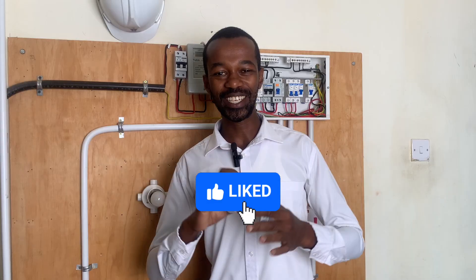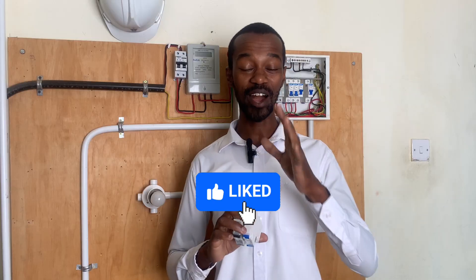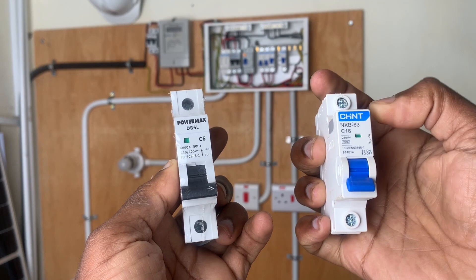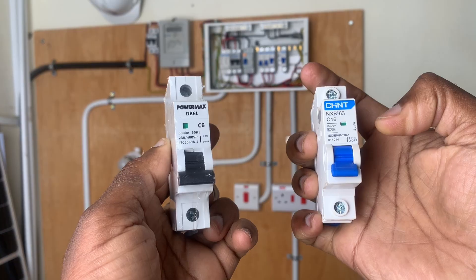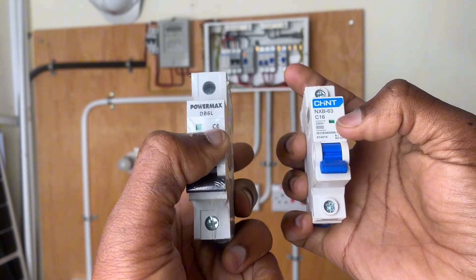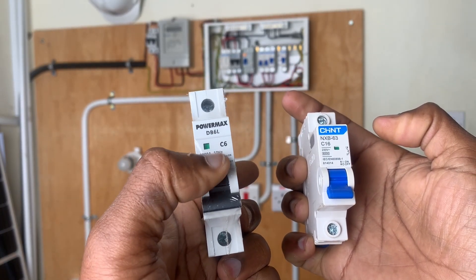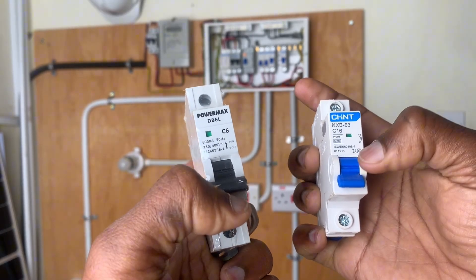An MCB is very important, and the size of that MCB matters. I have two MCBs here — a 6 ampere and a 16 ampere. They are from different brands: Powermax and Chint. But that doesn't matter as much as the numbers. The 6 ampere means it can only allow less than 6 amperes; anything above this will definitely lead to its tripping. The 16 ampere is what we use for socket circuits.